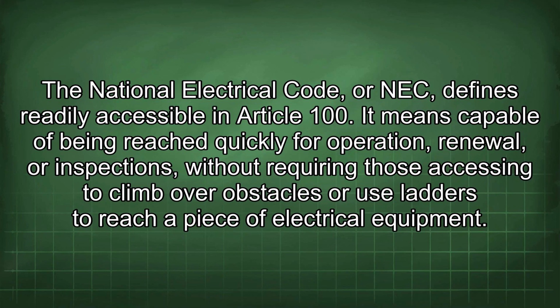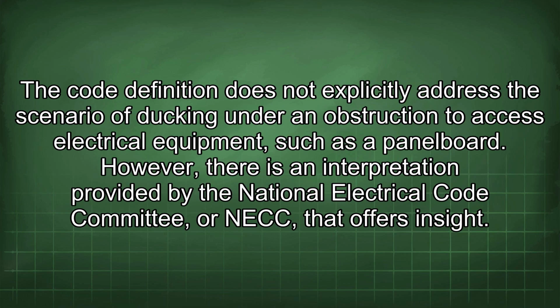The National Electrical Code, or NEC, defines readily accessible in Article 100. It means capable of being reached quickly for operation, renewal, or inspections without requiring those accessing to climb over obstacles or use ladders to reach a piece of electrical equipment. The code definition does not explicitly address the scenario of ducking under an obstruction to access electrical equipment, such as a panel board. However, there is an interpretation provided by the National Electrical Code Committee, or NECC, that offers insight.